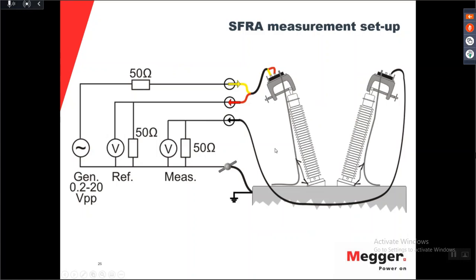The actual measurement circuit is a generator capable of generating a voltage, typically 20 volt peak to peak. The standard voltage now is 20 volt peak to peak. Here I usually mention, because it can be good to know, if I generate 20 volt here, my signal will go here, sorry, here, which means I have 50 ohm and 50 ohm, and I have my measurement point between the two 50 ohm resistors, or the 50 ohm impedance, which means my applied voltage here is actually only 10 volt, half the voltage. So if I say I generate 20 volt here, I will get 10 volt here.